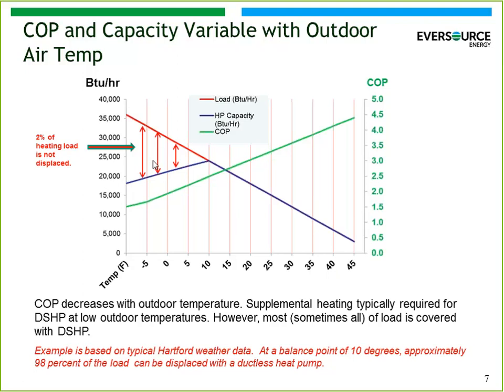When you're designing a heat pump, this is one of the challenges you face: what do you want to do with this little triangle? Do you want to eliminate it? You certainly can, but it means either putting in a larger heat pump or adding insulation or doing something to eliminate that triangle — in other words, it's going to cost more. Is it really worth the time, effort, and cost just to avoid 2% or 3% of the overall heating consumption?